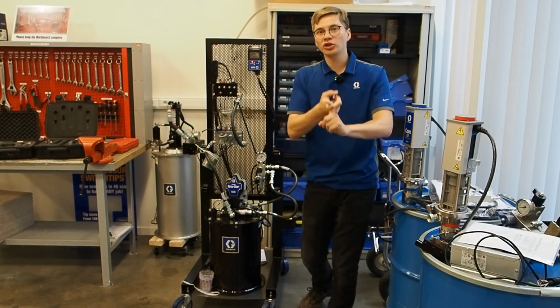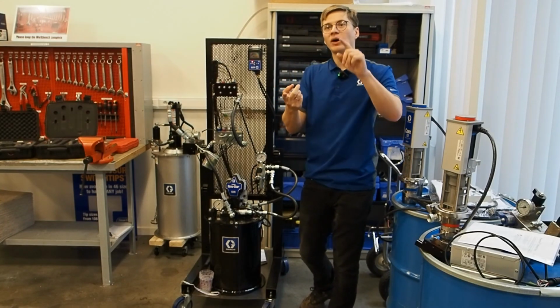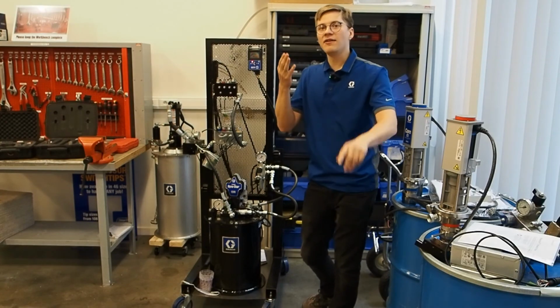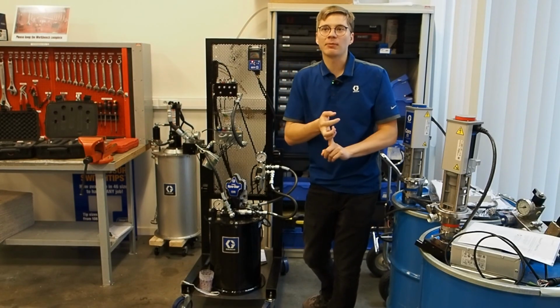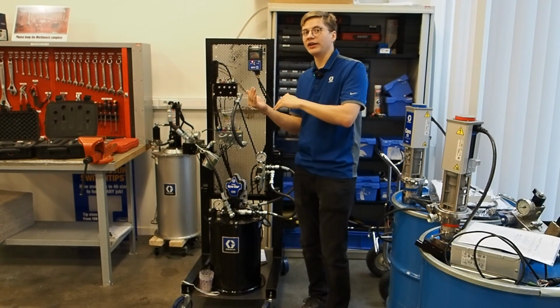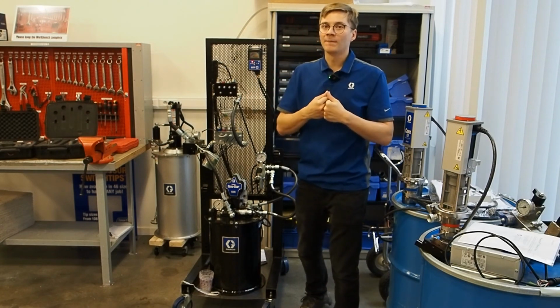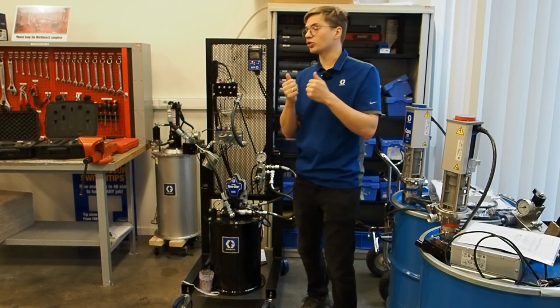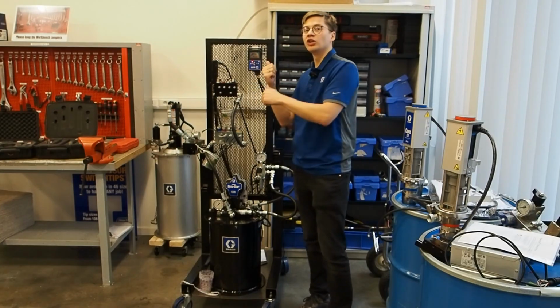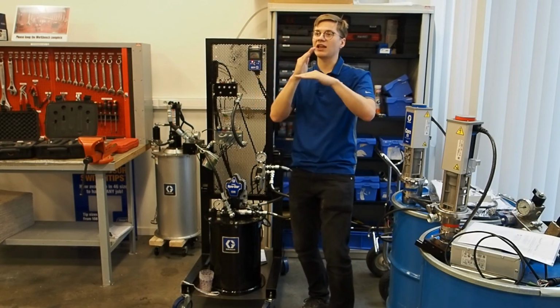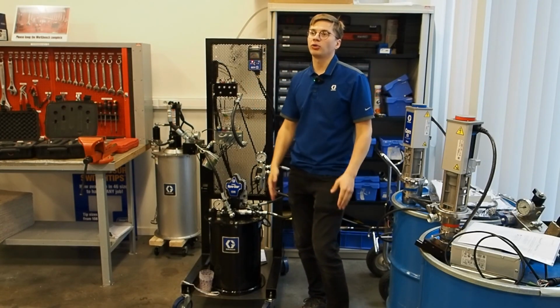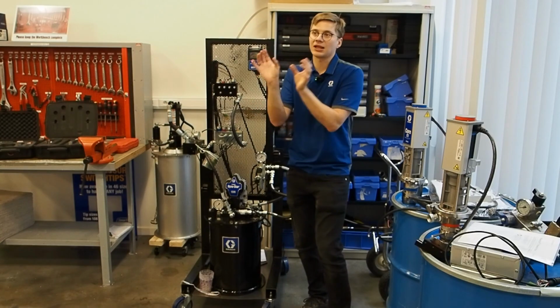Because it took 1 minute to build up pressure, and we have a 1 hour interval in the settings, we need 59 minutes of time off. If tomorrow is getting colder and it takes 3 minutes to build up pressure, then the time off will be 57 minutes. So the controller will adjust the time off itself to maintain a 1 hour interval. So it's every hour that we lubricate, because the interval is time on plus time off of the pump.